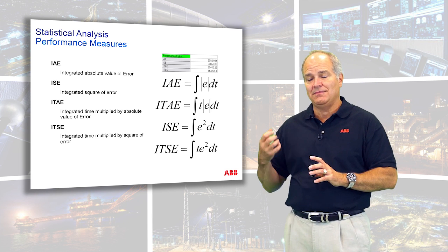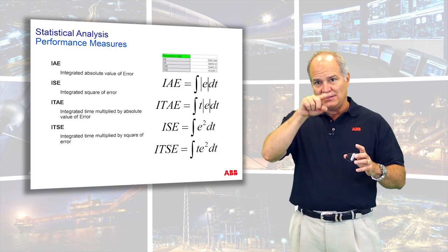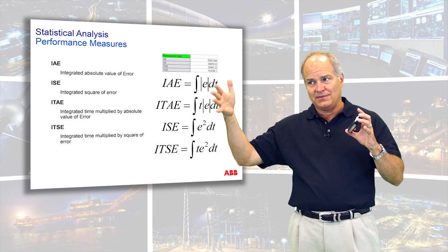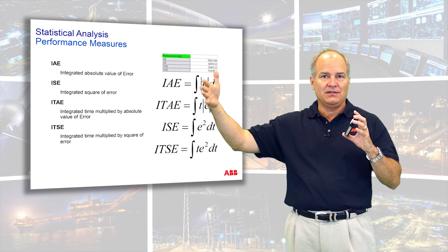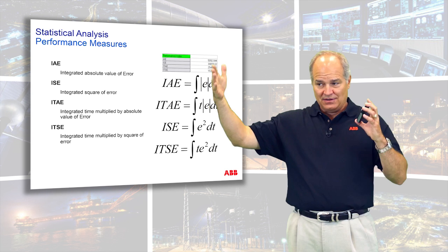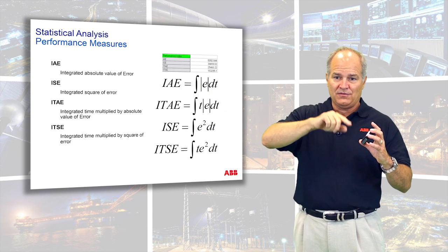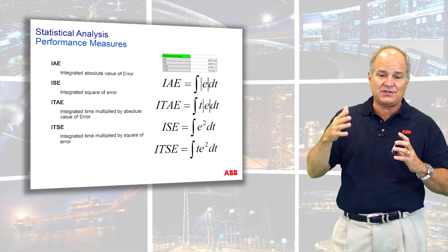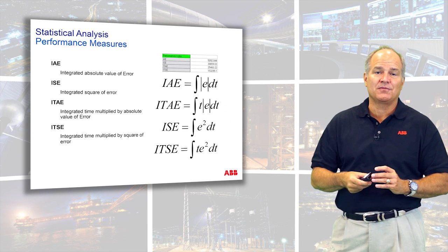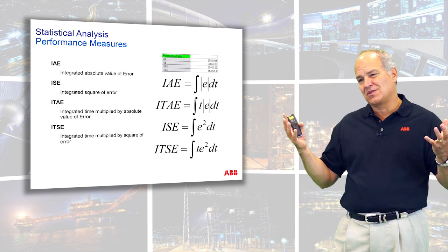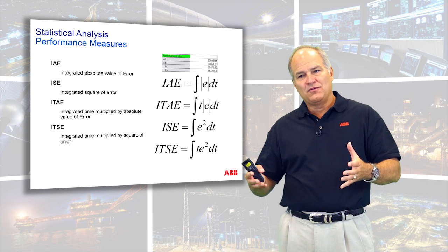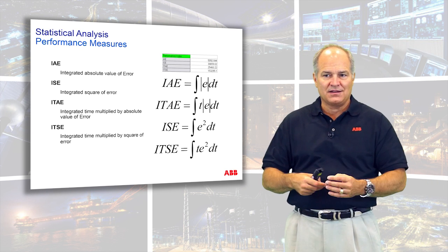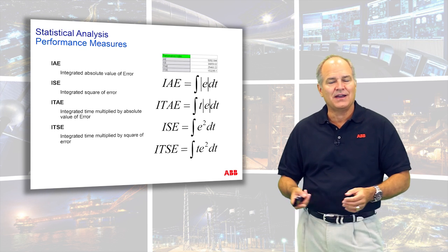I've used these to measure, like if I'm changing the set point and it takes a long time. It's the area between the set point and measured value. So I'll have a big number, and when I improve it, that area drops. The amount that it drops, or the ratio, is a measure of how well your performance did. These are classic performance measures that you'll see in a lot of different statistic evaluations.